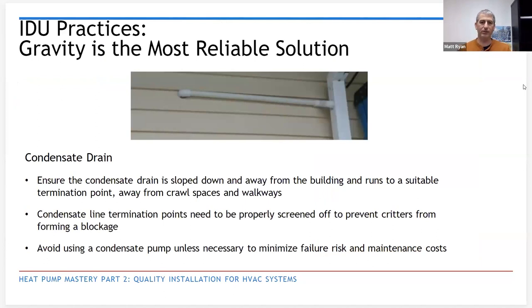So, kind of an interesting example we found there, but there's a lot of different ways to do that. Making sure it's run downhill, away from the building, away from being able to cycle back into a crawl space or a vent. Walkways, it's not ideal, in the middle of summer, to get this big old wet spot on your main entry to the house. It's not going to freeze. You're only going to have condensate in the summertime, but still just kind of an aesthetic thing there.